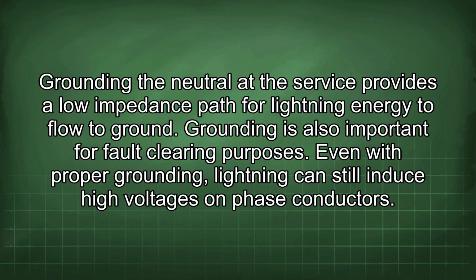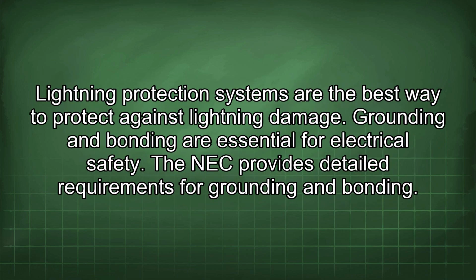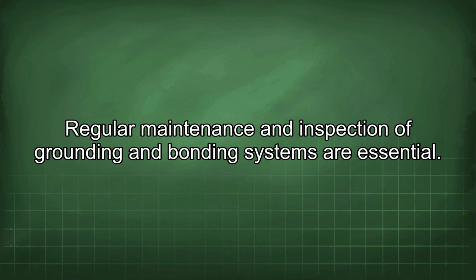Grounding the neutral at the service provides a lower impedance path for lightning energy to flow to ground. Grounding is also important for fault clearing purposes. Even with proper grounding, lightning can still induce high voltages on phase conductors. Lightning protection systems are the best way to protect against lightning damage. Grounding and bonding are essential for electrical safety. The NEC provides detailed requirements for grounding and bonding. Regular maintenance and inspection of grounding and bonding systems are essential.